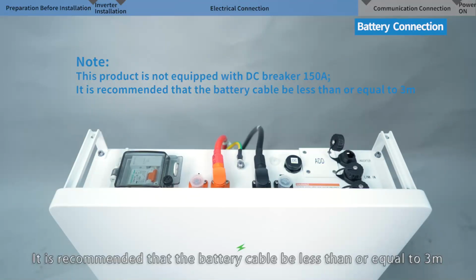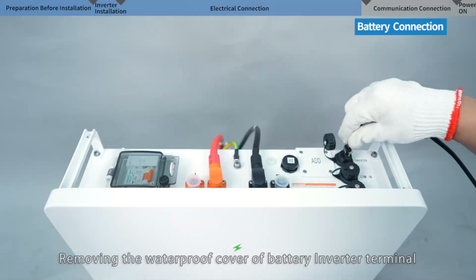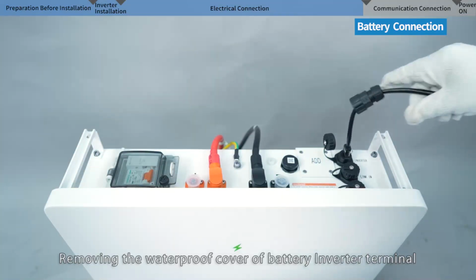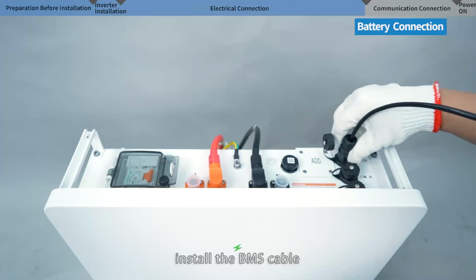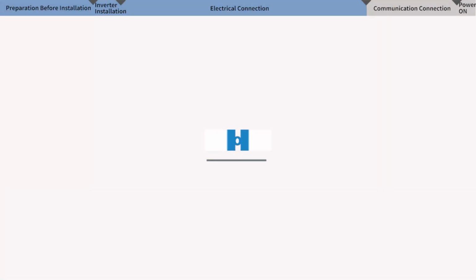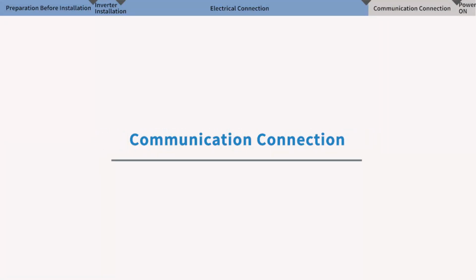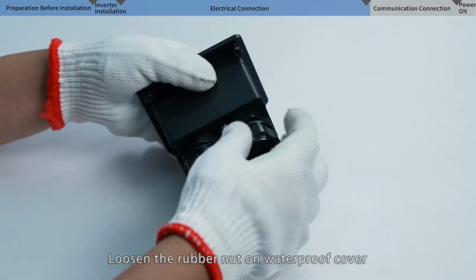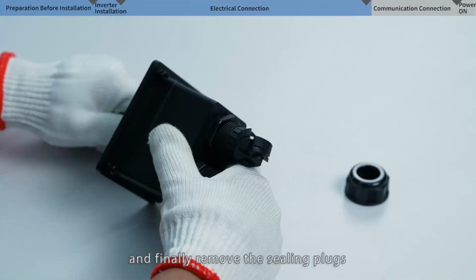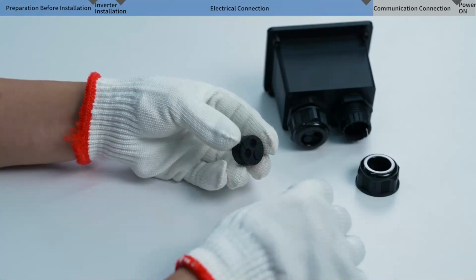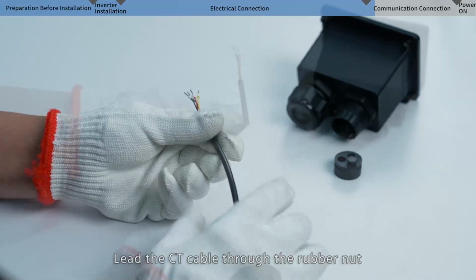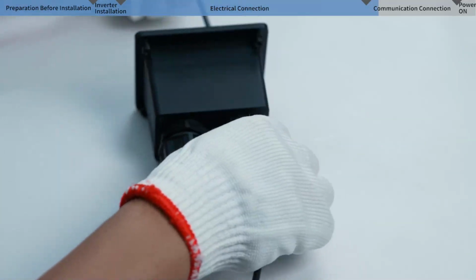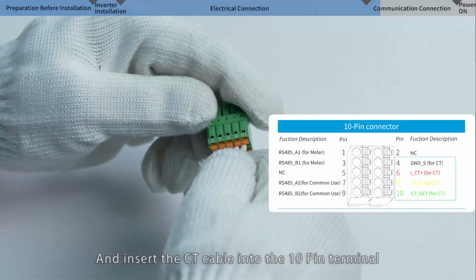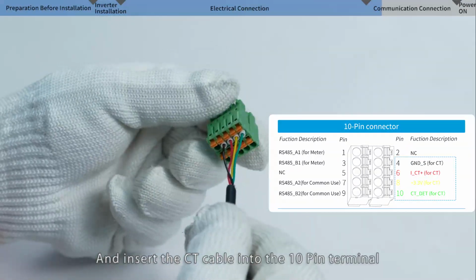It is recommended that the battery cable be less than or equal to 3 meters. Removing the waterproof cover of battery inverter terminal. Install the BMS cable. Loosen the rubber nut on waterproof cover and finally remove the sealing plugs. Lead the CT cable through the rubber nut, seal, and waterproof cover in turn. And insert the CT cable into the 10-pin terminal.